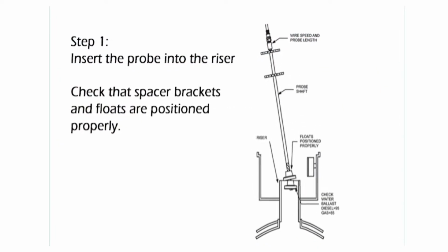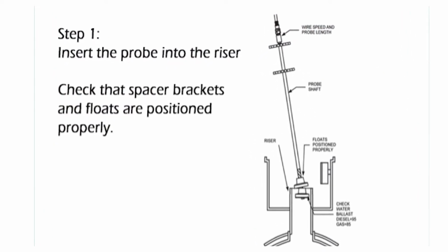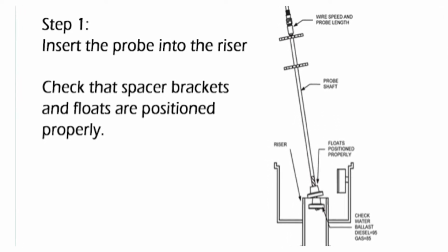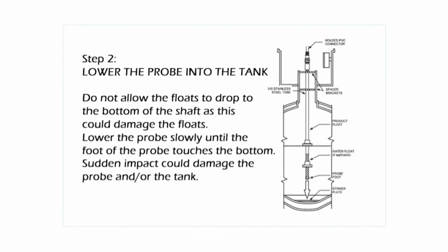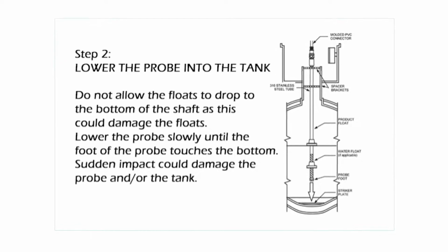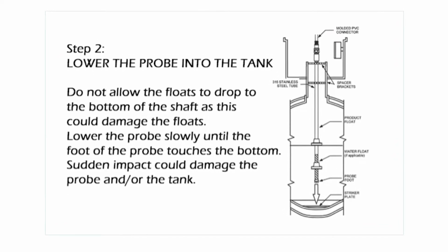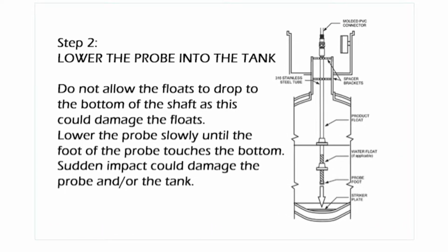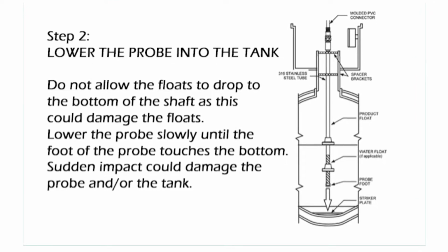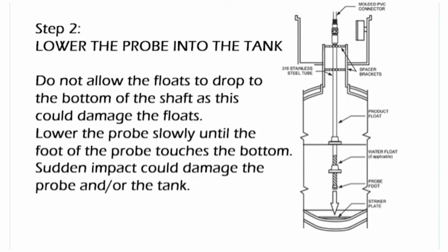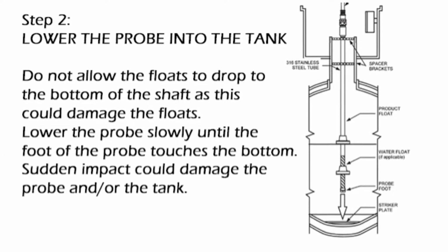Step 1. Insert the probe into the riser. Ensure the spacer brackets and floats are positioned properly. Step 2. Lower the probe into the tank. Do not allow the floats to drop to the bottom of the shaft, as this could damage the floats. Lower the probe slowly until the probe foot touches the bottom. Sudden impact could damage the probe and/or the tank.